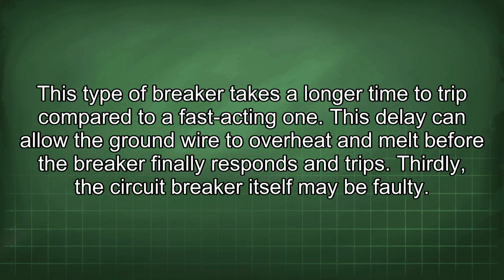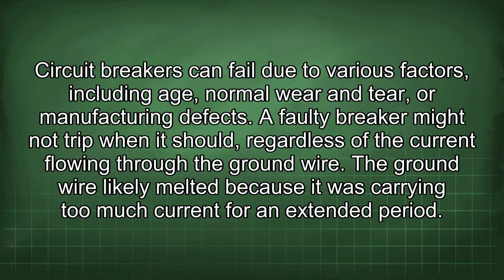Thirdly, the circuit breaker itself may be faulty. Circuit breakers can fail due to various factors, including age, normal wear and tear, or manufacturing defects. A faulty breaker might not trip when it should, regardless of the current flowing through the ground wire.